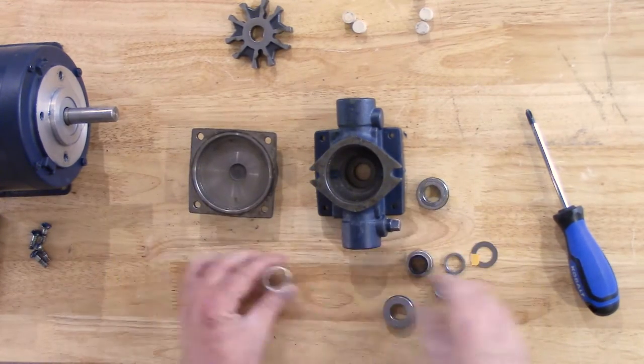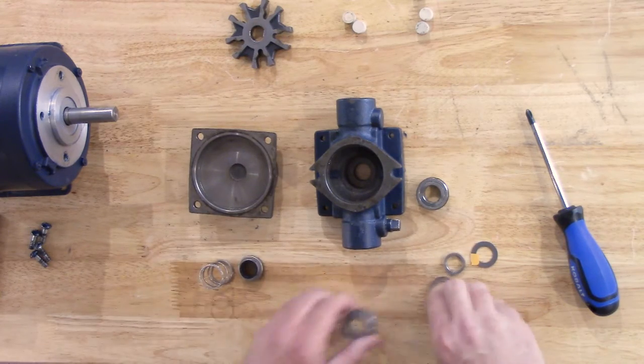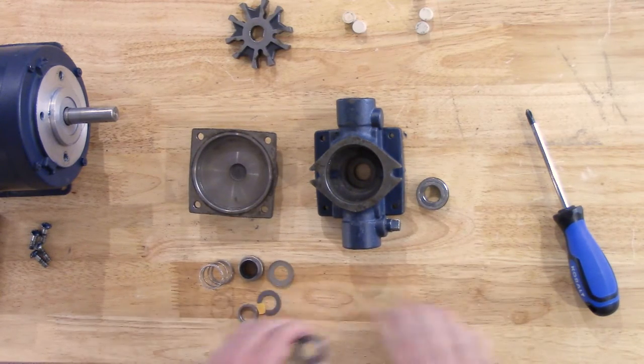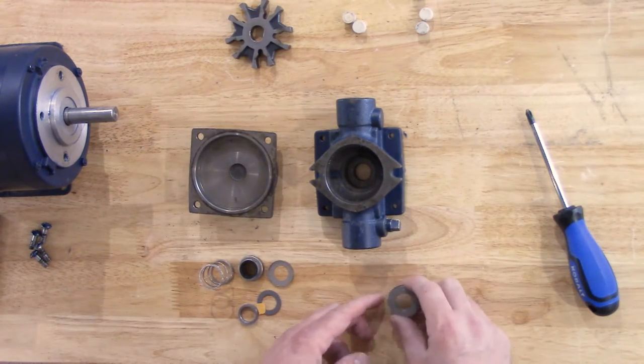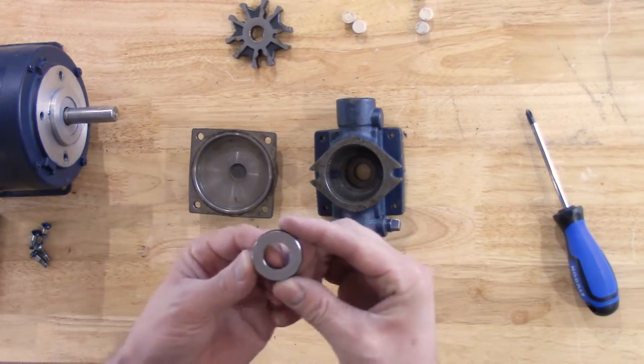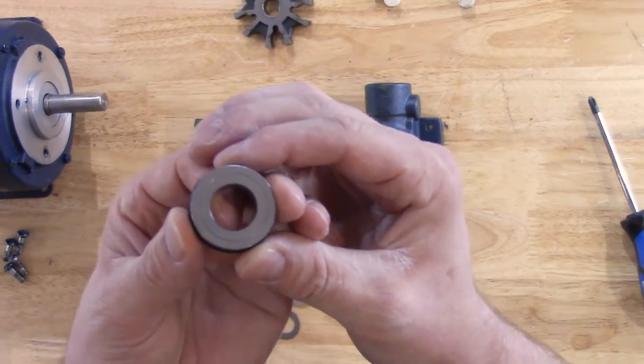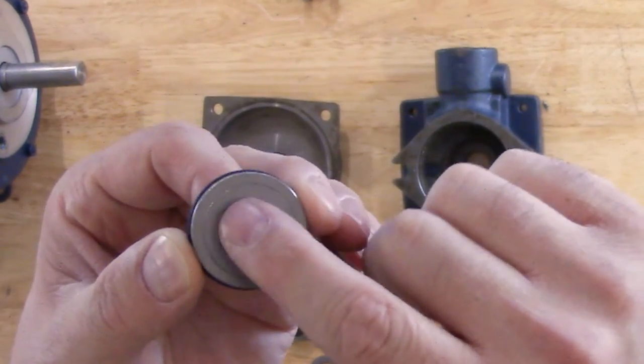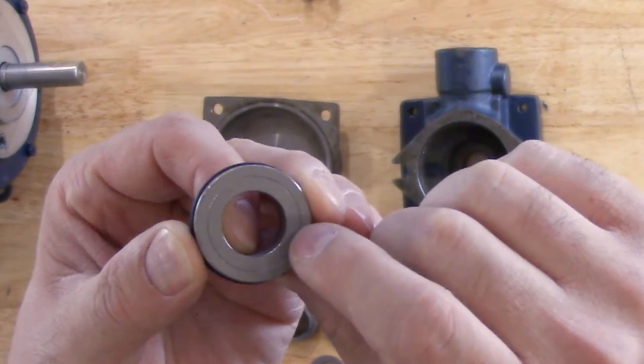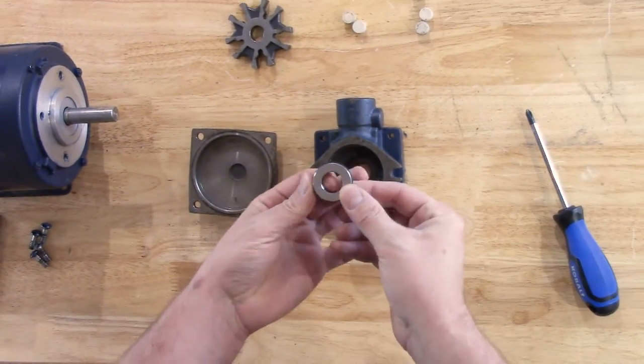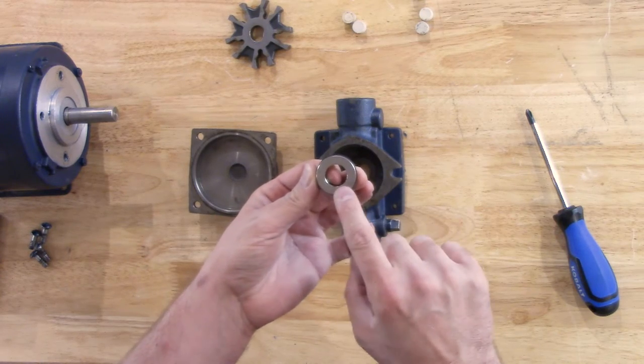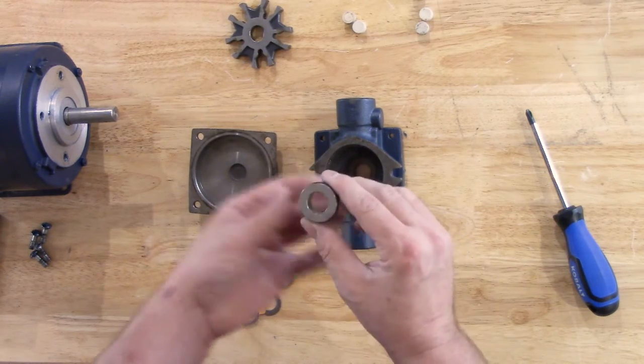Once we have our new seal kit parts out, we can set the shaft side over to the side as we don't need those currently. We can take our old seal and set it out of the way. Now that we have our new seal, we want to pay special attention to the side that has the groove in the seal. This side will go face down inside the pump to where the shiny side of this will be facing our motor.